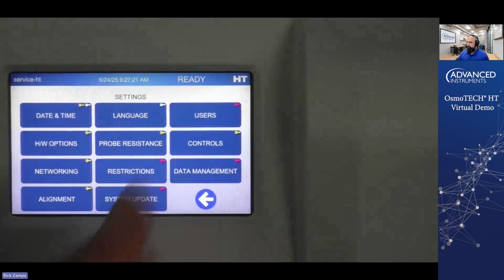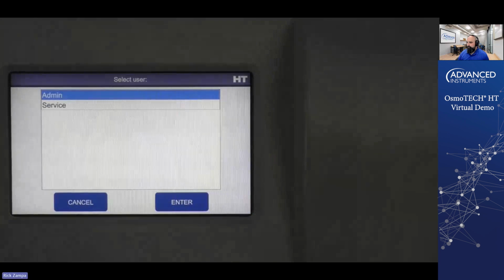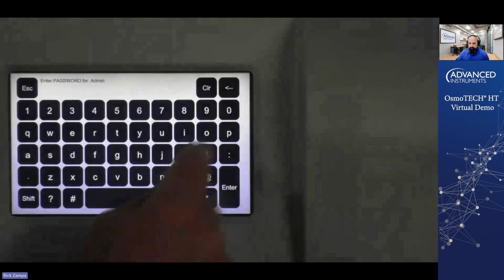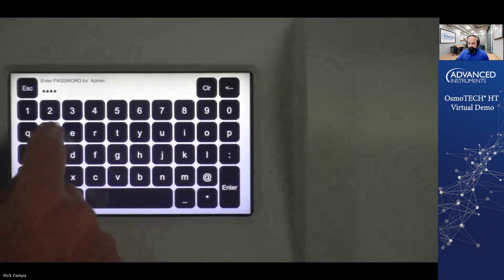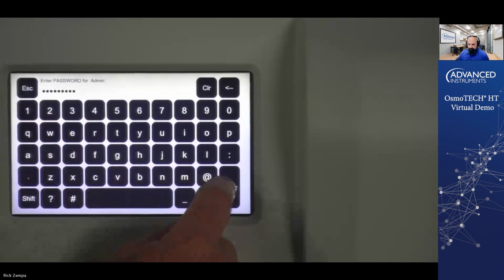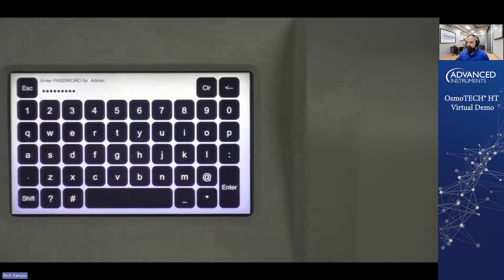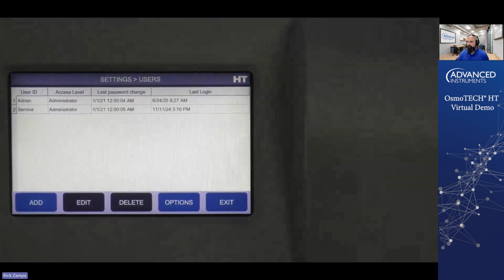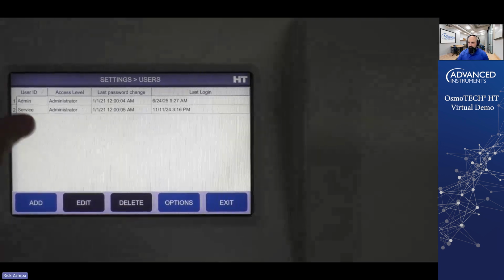So first thing I want to talk about is users. If you're going to set this up for a GMP environment, or for any environment for that matter, and you want to know who's doing the testing, you want to have users logged into the system. So what we do is we want to log into the system. Again, we're logging into every menu item so that we can ensure that we get the proper documentation into the audit trail when we go to talk about that. So you can see here we only have 2 users added to the system, the administrator and the service account.